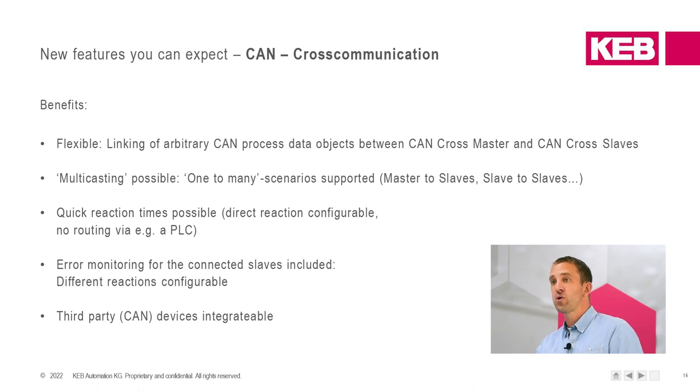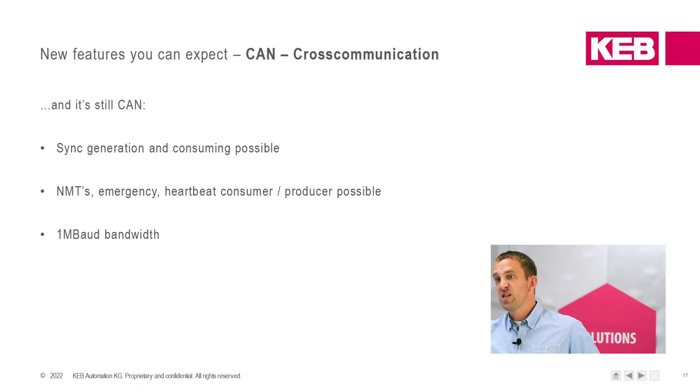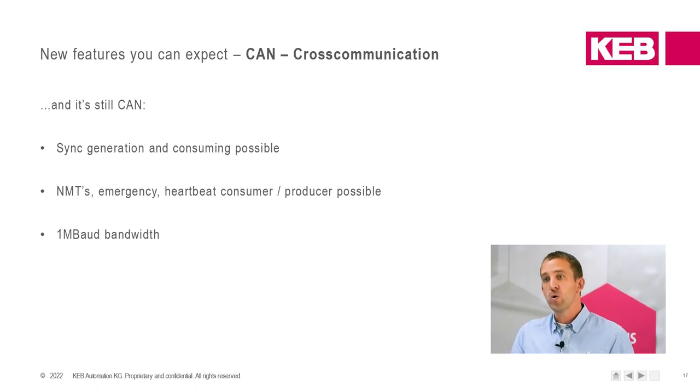And last but not least, it is also possible to include even third-party devices as long as they are able to speak CAN. And in the very end, it is still CAN. So that means we have all the well-known CAN communication principles and side elements of the protocol available, including sync generation and consumption, including NMT, including emergency telegrams, heartbeat consumer and producer, etc. And we still have the well-known baud rate that is currently implemented in the generation 6 drives, of 1 megabaud available solely, if you want, for the inter-drive communication.